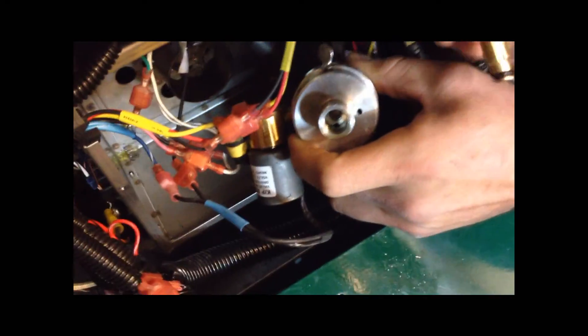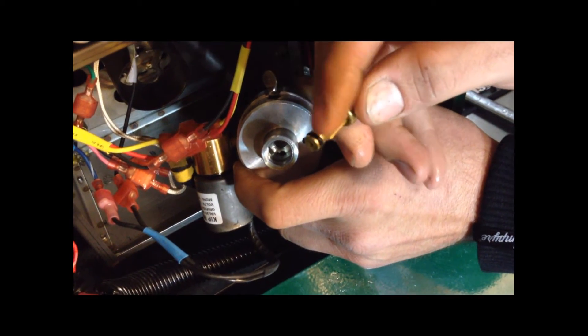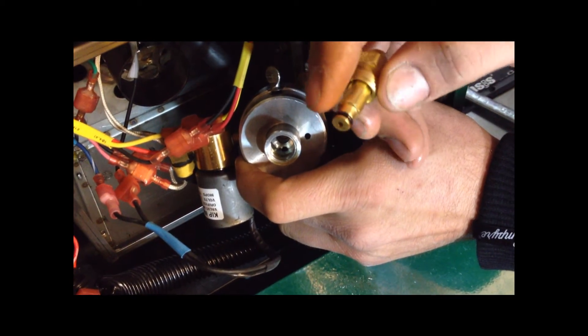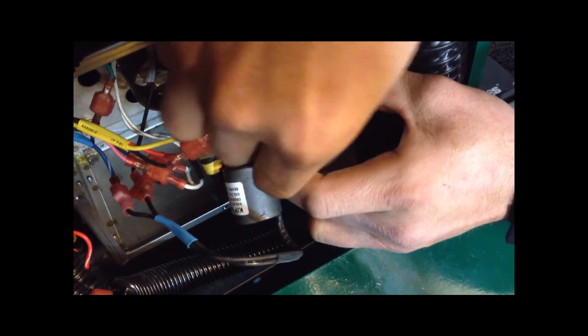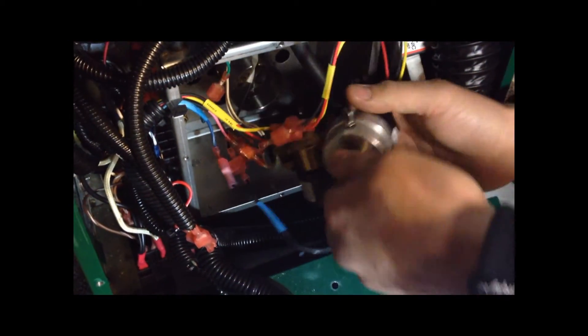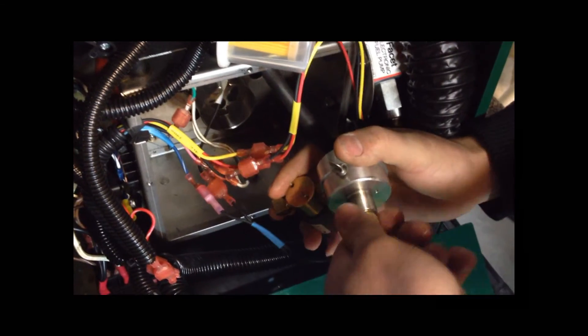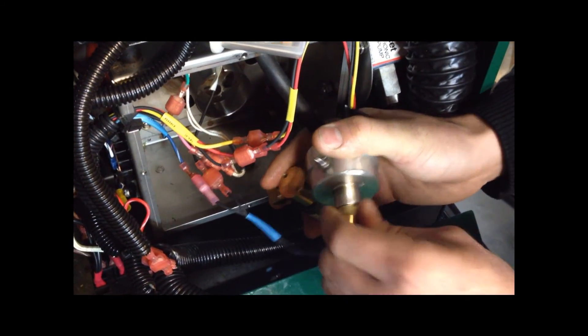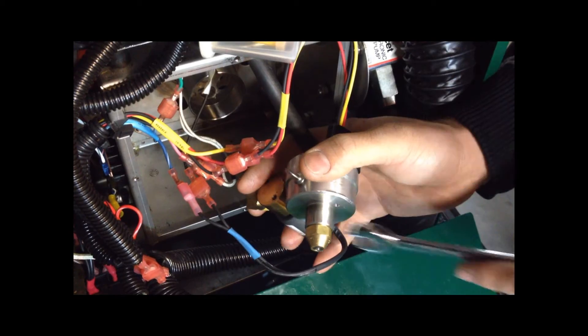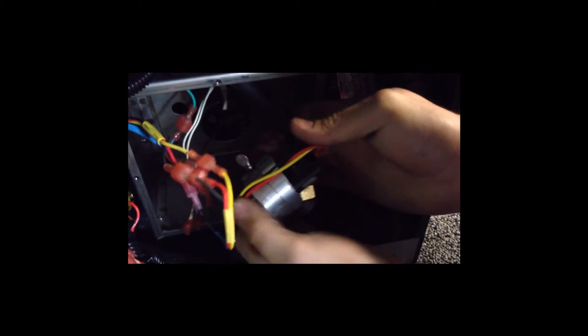Before reinstalling the nozzle, lubricate the O-ring to prevent it from pinching. When tightening down the nozzle, make sure the nozzle seats itself all the way up against the fuel block and just snug it down. Now you can put the fuel block back in the burn tube. Fuel block back in. Tighten that thumb screw back up.